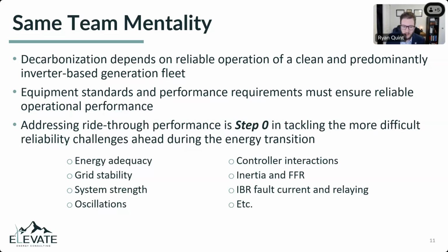Things like energy adequacy, wildly changing grid stability margins, a drop in system strength, and how we plan to manage that with new forms of controllers, new grid-forming inverters, etc. We're seeing an increase in oscillation, a decrease in system damping, notable controller interactions, plants doing erroneous things after they've been commissioned, a decline in system inertia and the need for fast frequency response, and a whole new environment of protective relaying, fault current injection, etc. Those are very challenging things we all have to face, and very smart engineers around the world are tackling those things, but with the expectation that the resources are riding through basic grid disturbances.